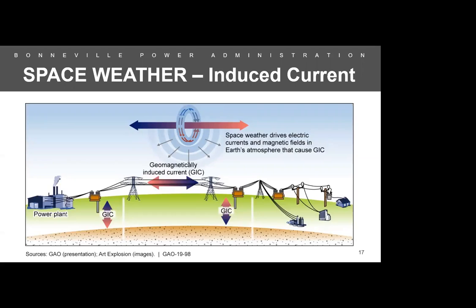These geomagnetic induced currents from solar events result from differences in potential of the Earth's crust over large distances. Current begins to flow in whatever conductive material exists between points of different potential. At locations where BPA or other utilities have long transmission lines, particularly with grounded transformers on each end, the line becomes an attractive path for these currents, and it can wreak havoc on the power grid, especially on our transformers, which have long lead times and are costly to repair and replace.